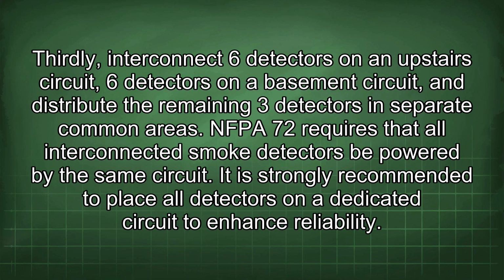Thirdly, interconnect 6 detectors on an upstairs circuit, 6 detectors on a basement circuit, and distribute the remaining 3 detectors in separate common areas. NFPA 72 requires that all interconnected smoke detectors be powered by the same circuit. It is strongly recommended to place all detectors on a dedicated circuit to enhance reliability.